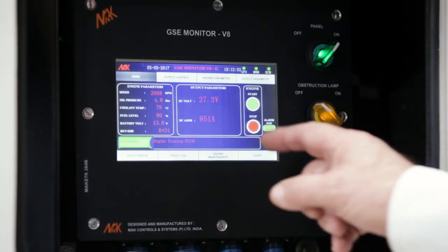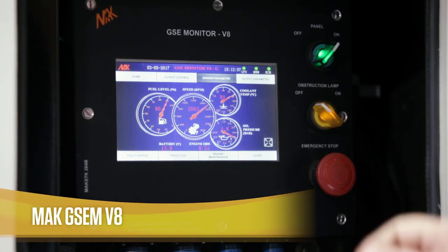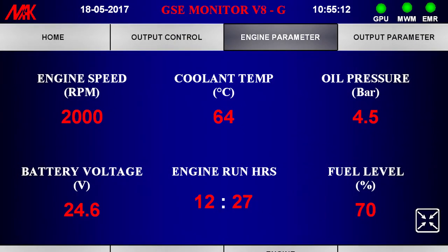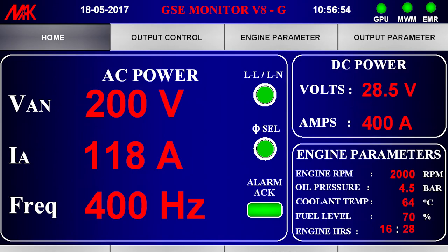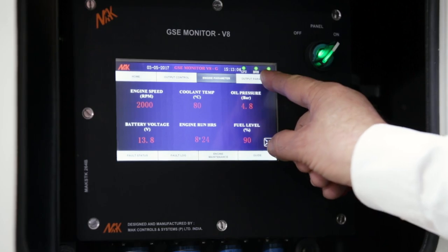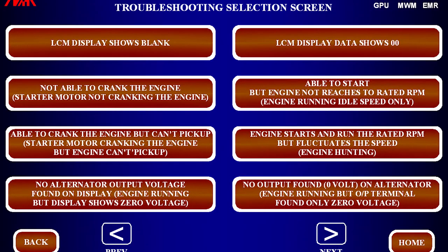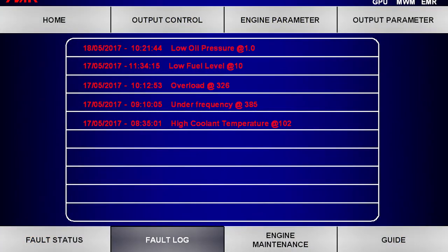Our digital interactive touchscreen control panel, called the MAK GSEM V8, is standard across all our GSE and is a unique feature in this industry. The unit features a single screen which displays vital parameters of the engine and alternator, including engine RPM, oil pressure, coolant temperature, fuel level, current consumption, battery voltage, and all output parameters, making the operator's job effortless. It also has a troubleshooting guide to help solve any issues quickly and effectively. To understand the equipment status, one may refer to the scheduled maintenance details and fault log chart.